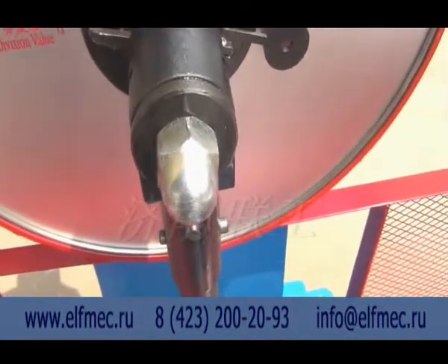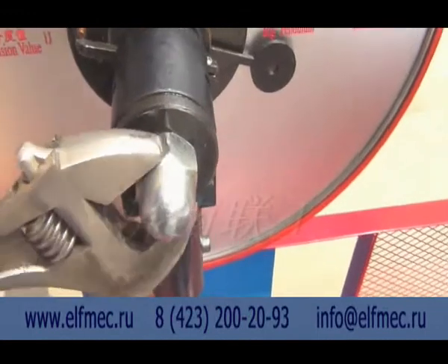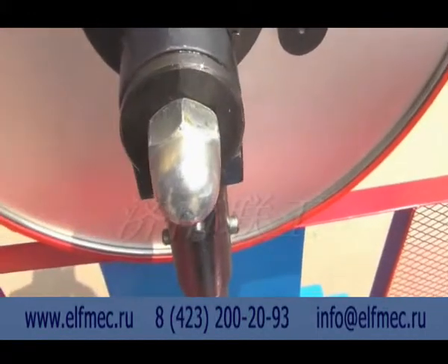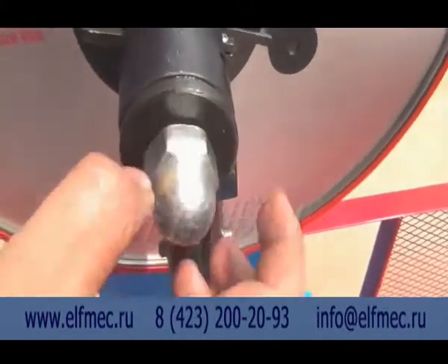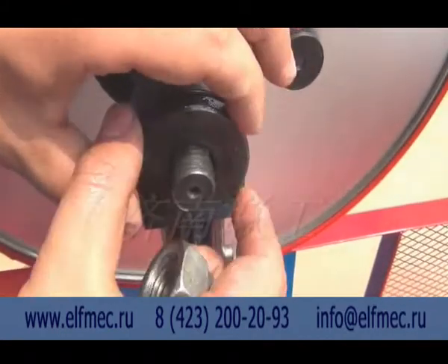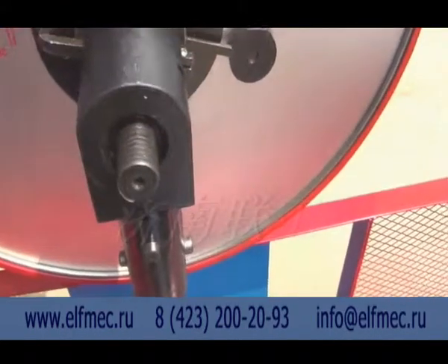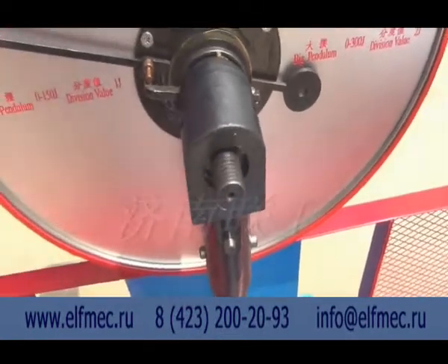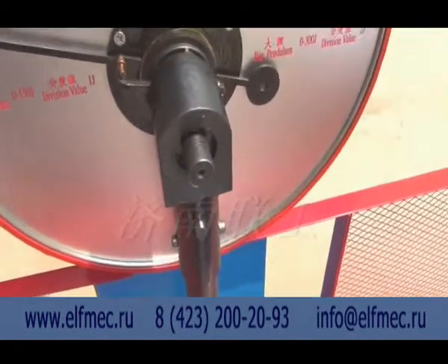Pendulum replacement. Choose a suitable pendulum according to the using scope and the endurance of the samples. Change mode: loosen the lock nut. Use a special demolition device to disassemble. Take down the pendulum, replace it with a suitable pendulum, and lock the nut.